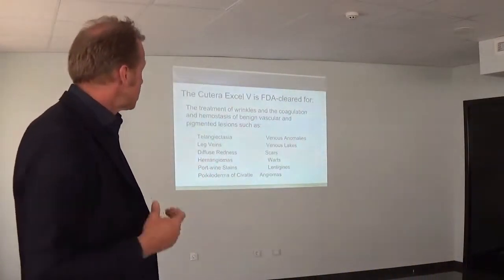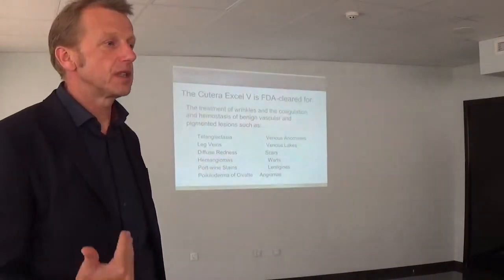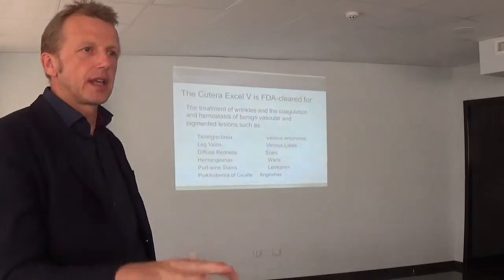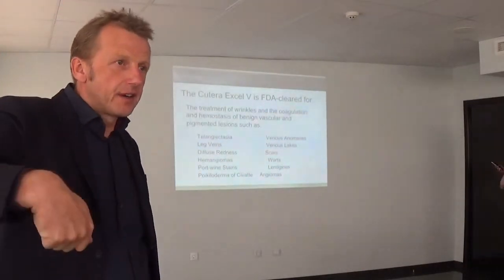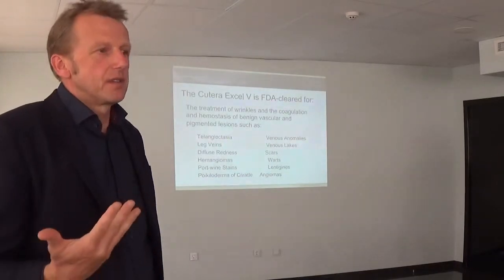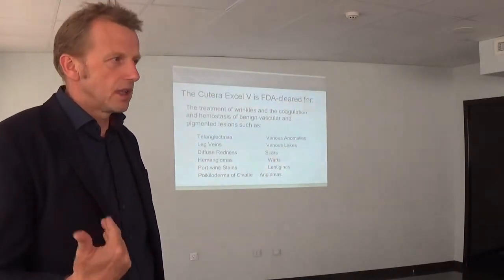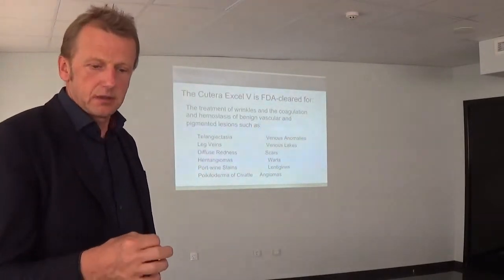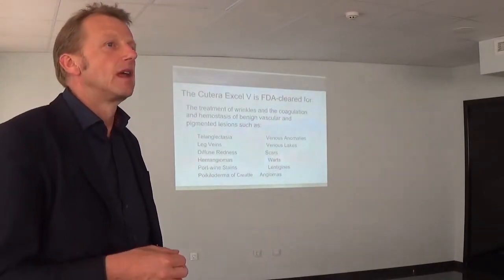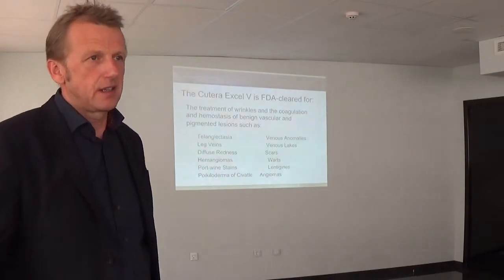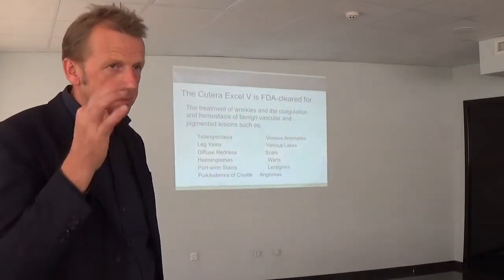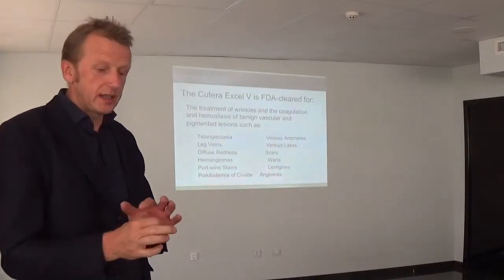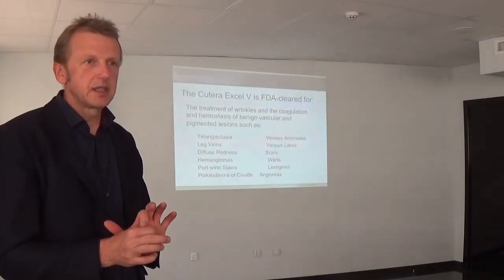And then that survey with those specialists showed that they didn't like the spray cooling that Candela uses. They didn't like the air cooling because it's not so controlled. So the laser users that we inquired all prefer this contact cooling with sapphire, because of that index matching, because it's a perfectly controlled cooling to a certain temperature. With that index matching, you also have better visibility.